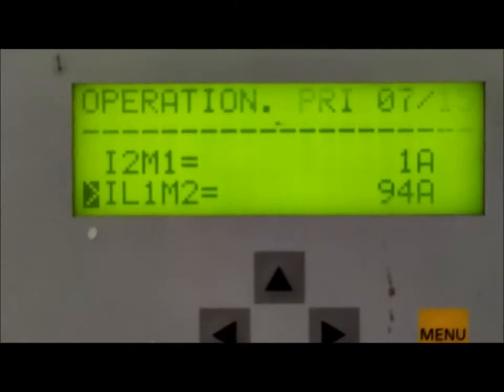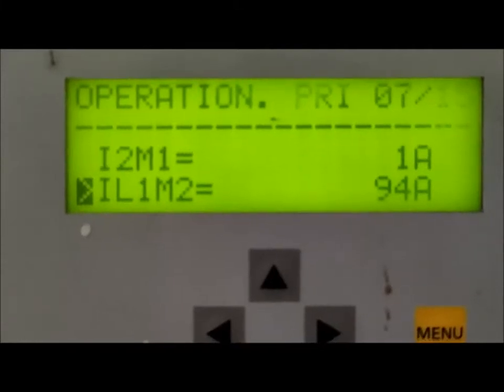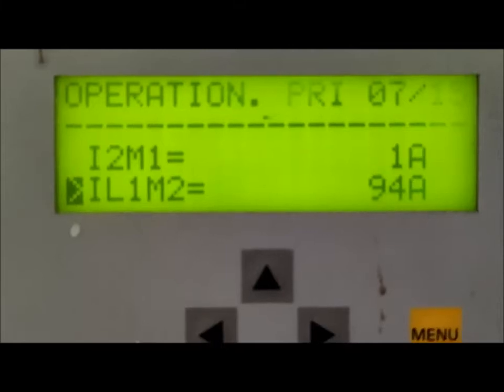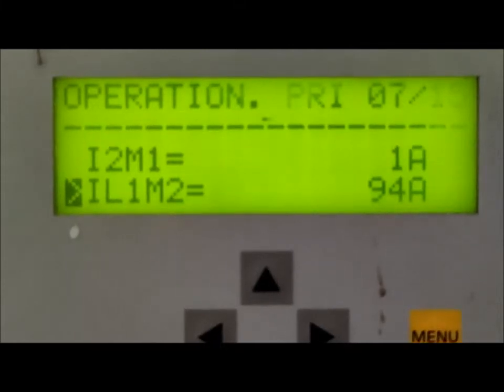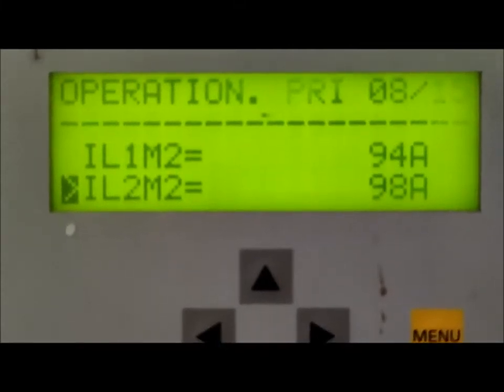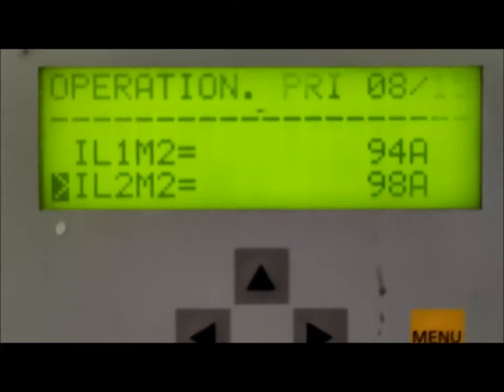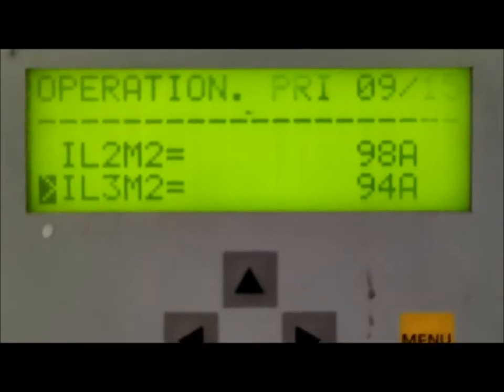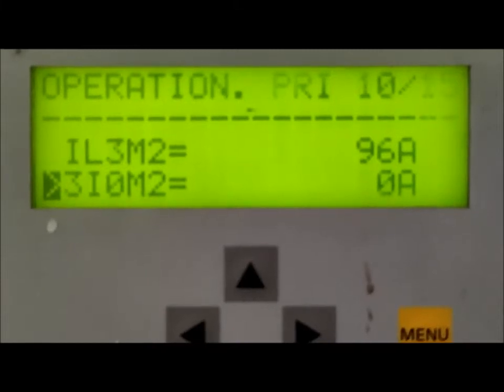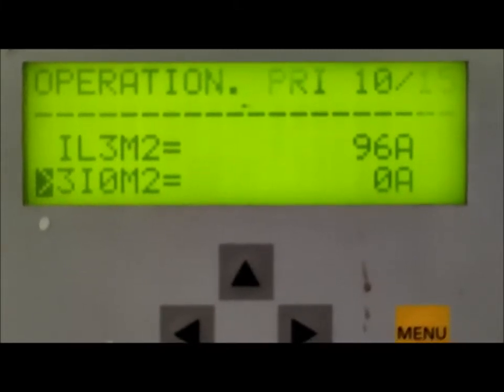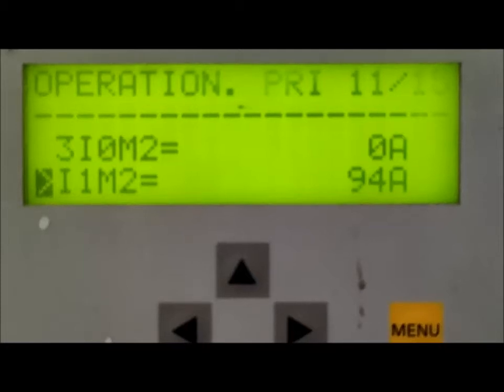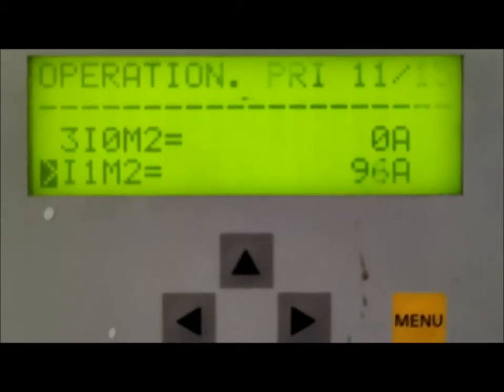IL1M2 is the LV side current, which is 94 amperes. IL2M2 is the Y phase current of the LV side, which is 98 amperes, and IL3M2 is the B phase LV side current, which is 96 amperes. 3I0 is the zero sequence current and I1M2 is the positive sequence current on the LV side.